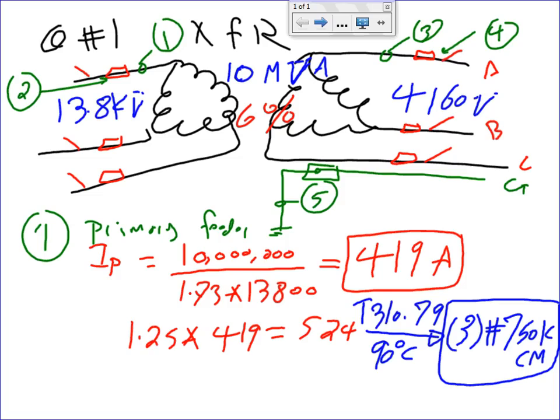So it's still the same calculation, guys. It's 1 circuit. It could be a multi-conductor cable, consisting of 3 insulated conductors cabled within an overall covering. So it's a 3 conductor cable in underground ducts, 1 cable per electrical duct, based on ambient.